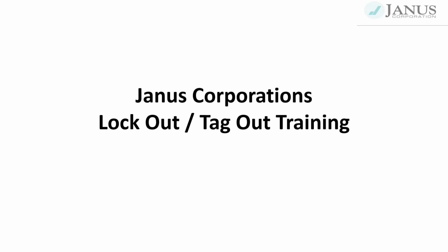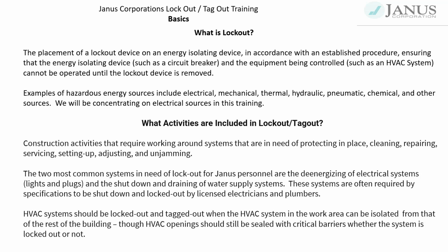Welcome to Janus Corporation's Lockout Tagout training, part of Janus's Injury and Illness Prevention Program. Lockout is the placement of a lockout device on an energy isolating device in accordance with an established procedure, ensuring that the energy isolating device, such as a circuit breaker, and the equipment being controlled, such as an HVAC system, cannot be operated or start automatically until the lockout device is removed.